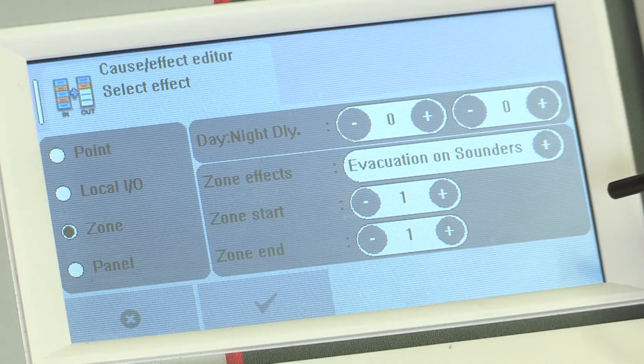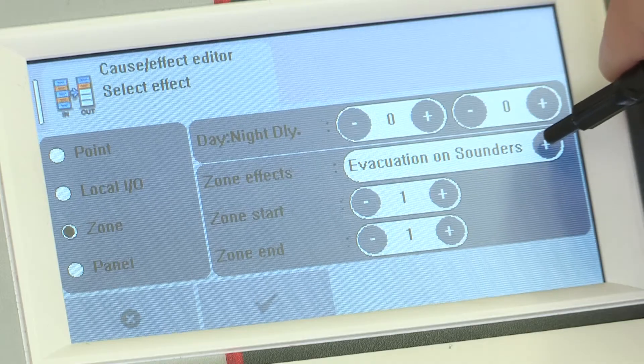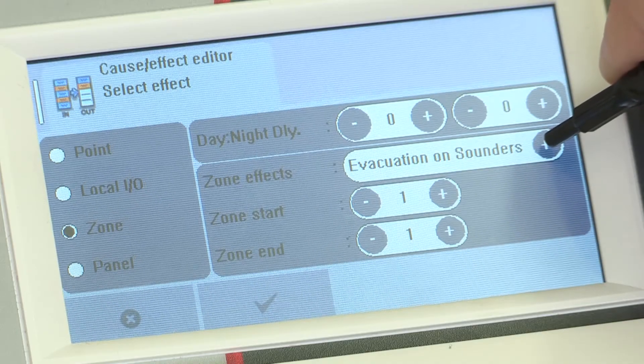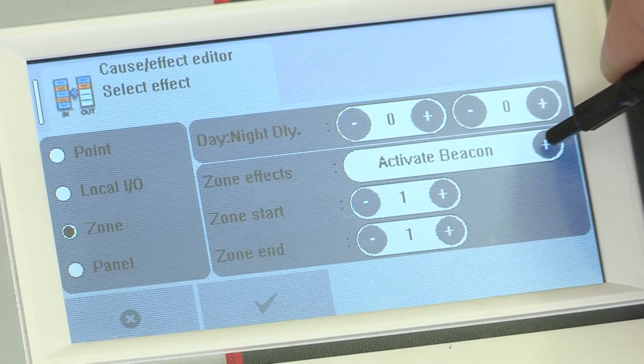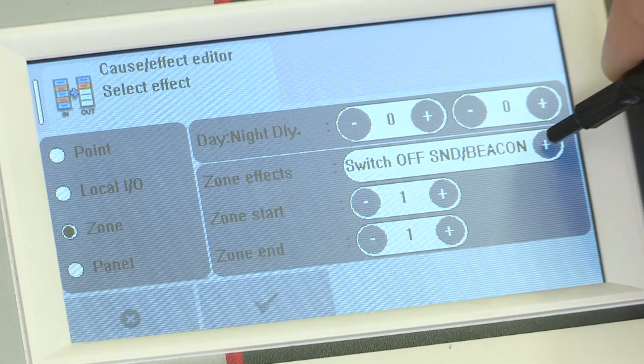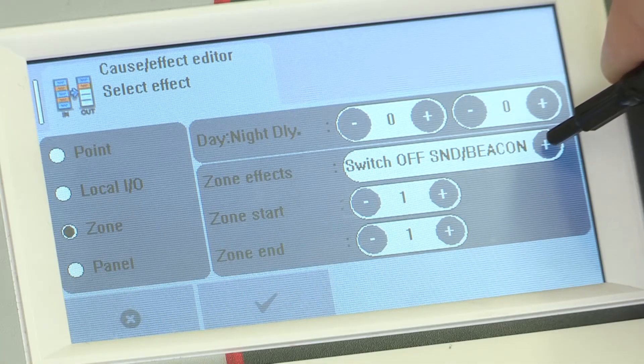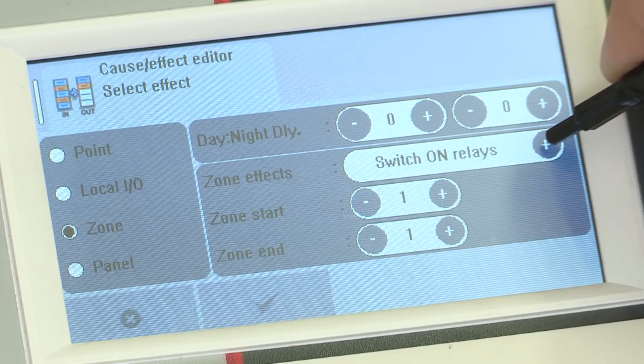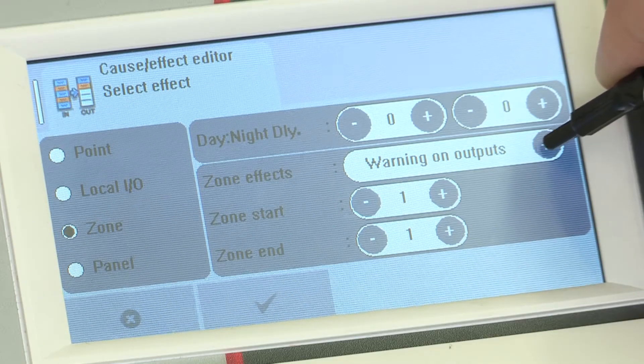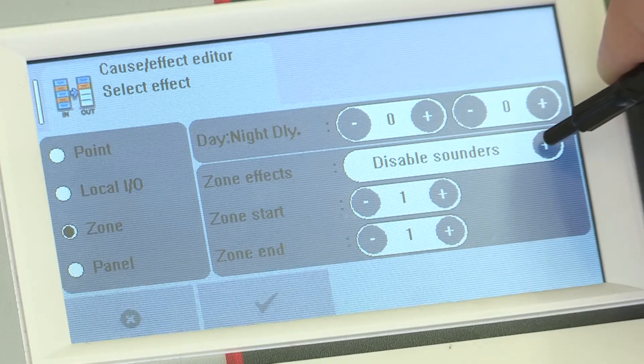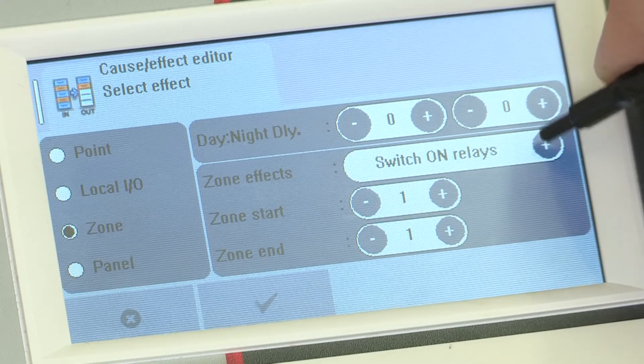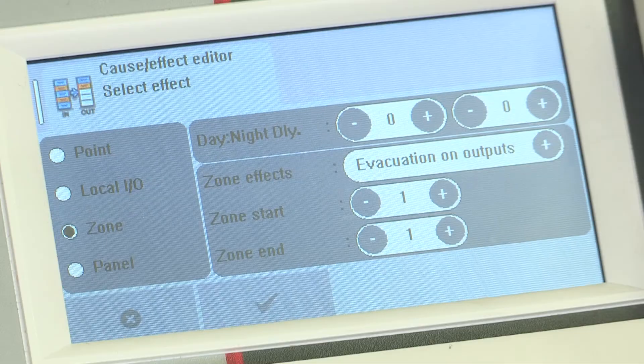You can select the effect itself as evacuation, warning, beacon, switch on, switch off, enable, or disable. In the case of zone or panel, there is an option to evacuate on outputs, which covers all relays, sounders, and beacons.